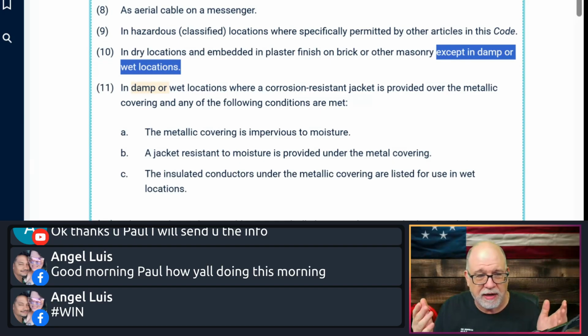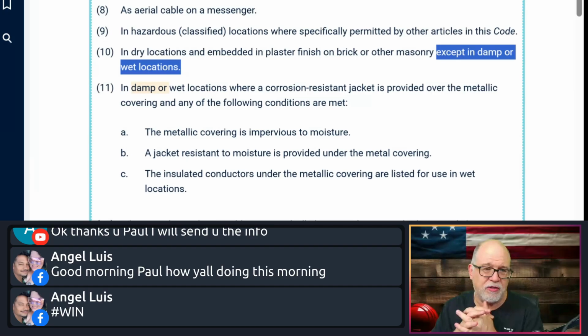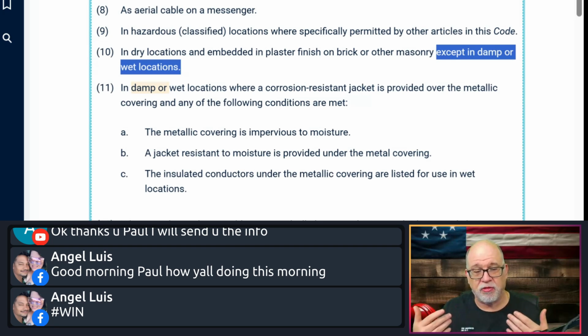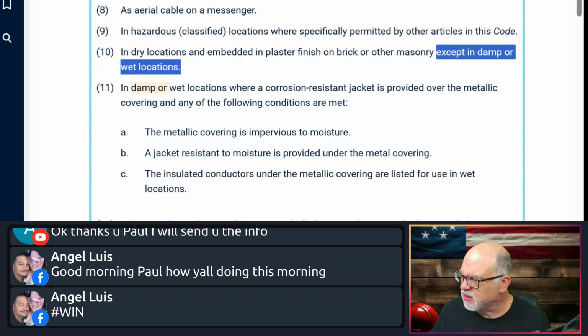That's what the product is rated for. But it's also allowed to be in certain things like plaster finish, embedded in that, as long as where you're doing it is not a damp or wet location, because that plaster is going to absorb moisture. Moisture is going to get into the plaster. The brick and masonry is going to hold that moisture. So you don't want that.